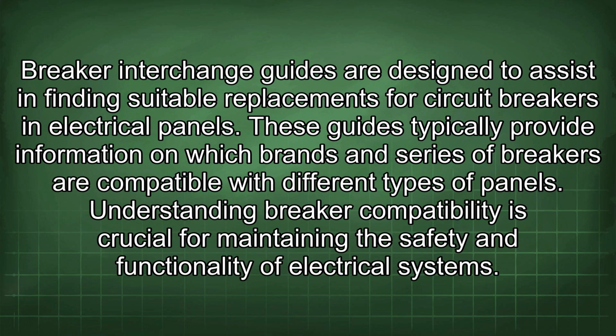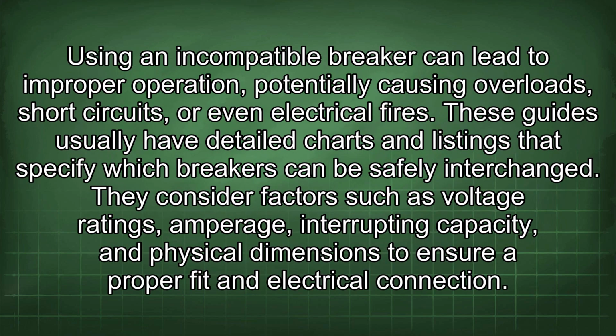Breaker interchange guides are designed to assist in finding suitable replacements for circuit breakers in electrical panels. These guides typically provide information on which brands and series of breakers are compatible with different types of panels. Understanding breaker compatibility is crucial for maintaining the safety and functionality of electrical systems. Using an incompatible breaker can lead to improper operation, potentially causing overloads, short circuits, or even electrical fires.